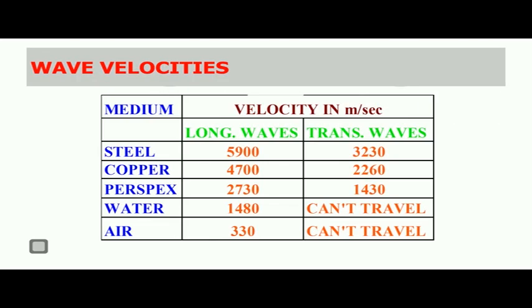The velocity of ultrasonic waves is a property of the material or medium in which they are travelling. The velocity depends on whether it is a longitudinal or transverse wave. In case of steel, the velocity of longitudinal waves is approximately 5900 m/s, whereas transverse waves travel at 3230 m/s. For perspex, longitudinal waves travel at 2730 m/s and transverse waves at 1430 m/s. In water, longitudinal waves travel at 1480 m/s, while transverse waves cannot travel through water. In air, the velocity of longitudinal waves is 330 m/s.